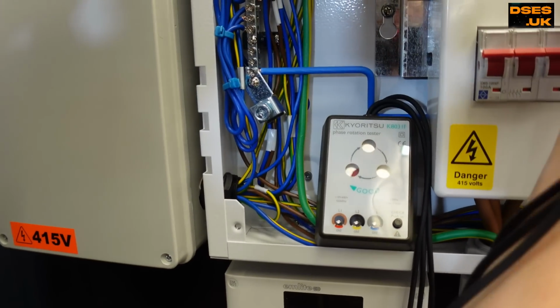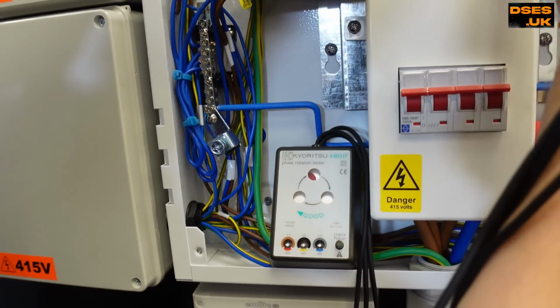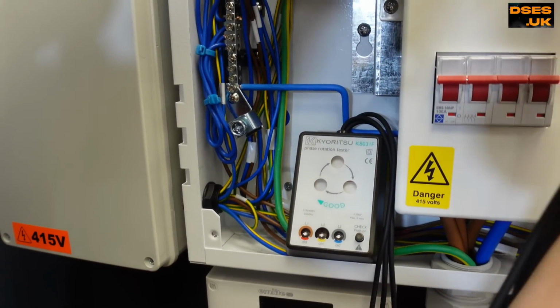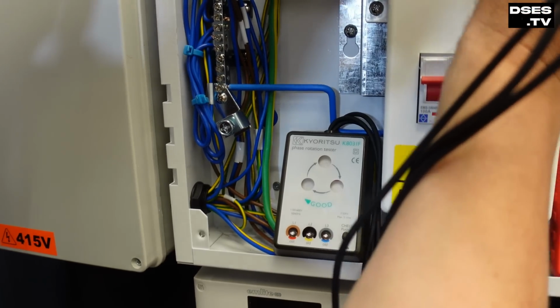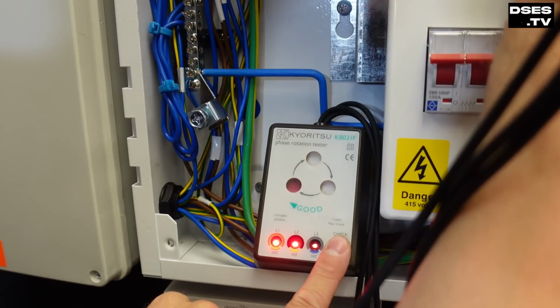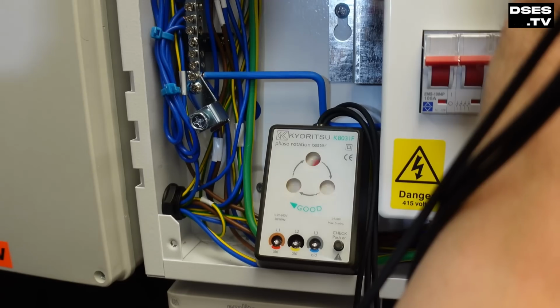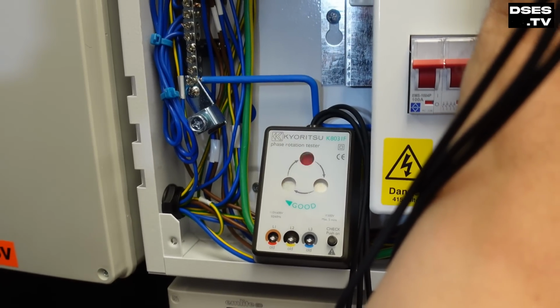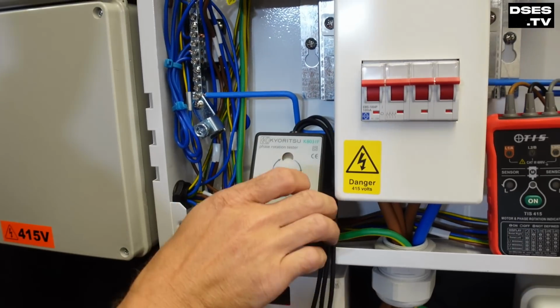If I were to swap 2 of the phases over, so it was grey, black and brown rather than brown, black, grey, if I press it now, you can see it's going backwards, which is bad by definition. But that's a mechanical 3-phase tester.